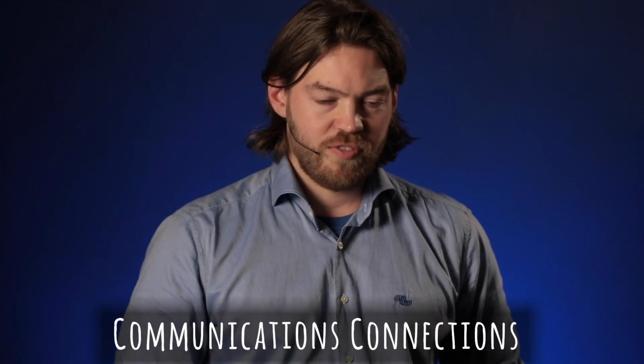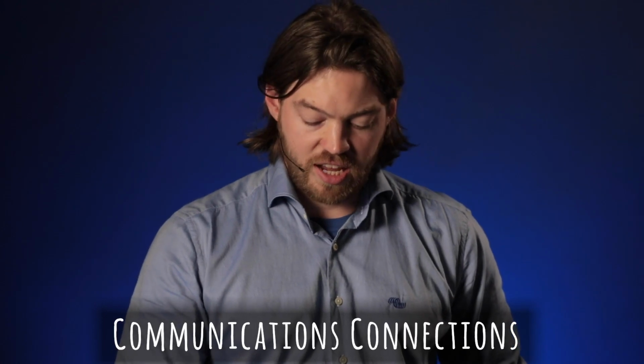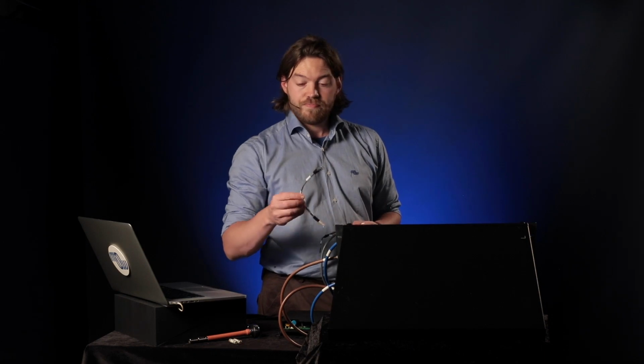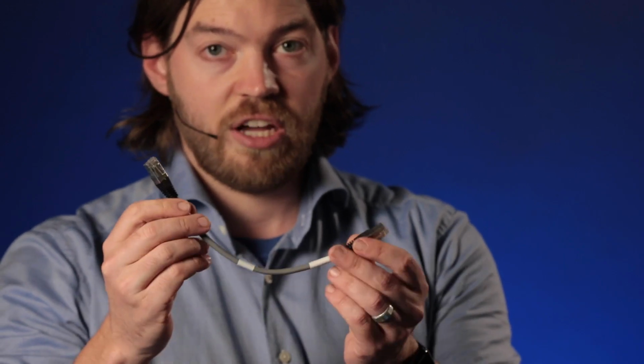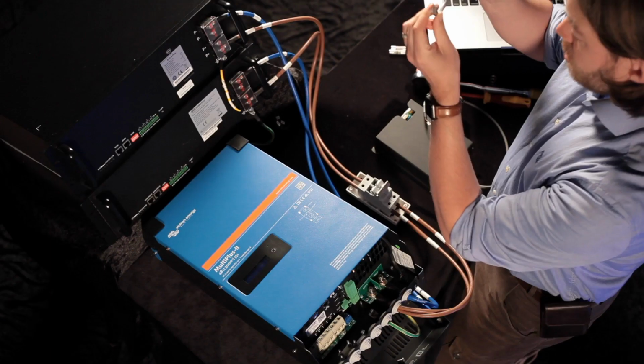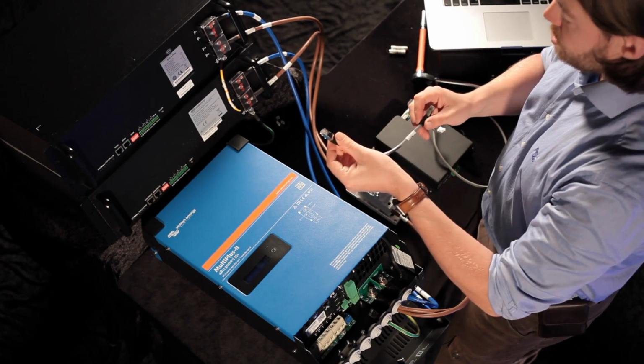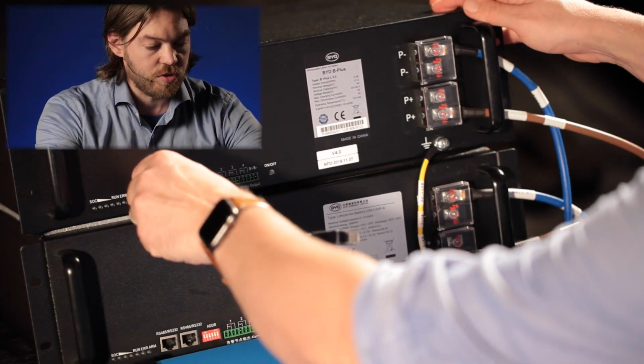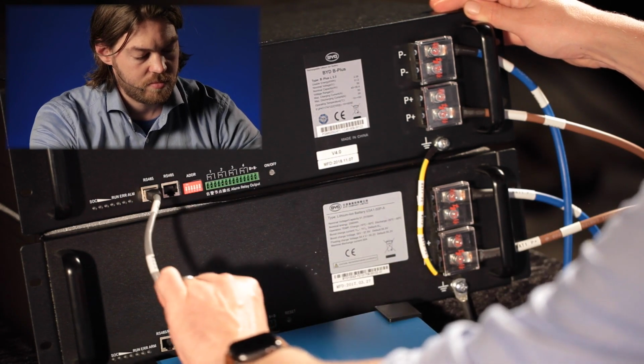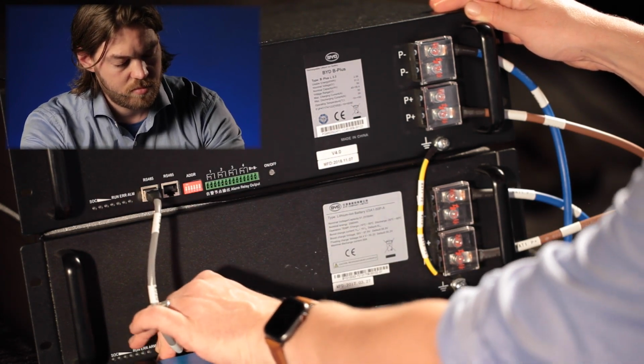step. We're now going to move on to making the communications connections and supplying power to the BMU. Now these parts, some come supplied with the BYD equipment, and some you have to purchase from Victron that are specific to connecting to Victron equipment. The first cables that come supplied with BYD equipment is this pass-through RS485, which is a Cat5 RJ45 connection cable. This goes between the battery modules themselves. This allows the batteries to talk to one another. That's good.